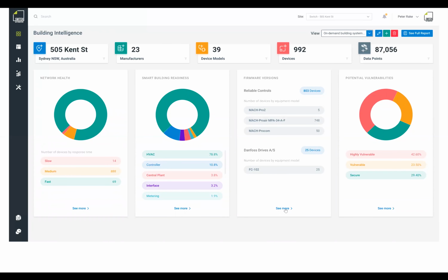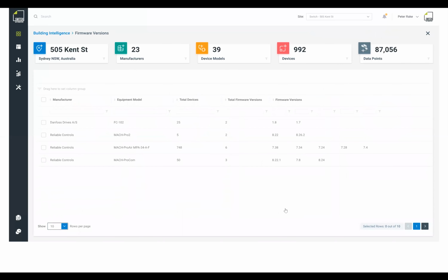Firmware is also another common potential vulnerability, with versions being really old, out of date, or exposing potential vulnerabilities. So in this scan here, you can see this particular piece of hardware had 5 different versions of firmware throughout this building. So now we're able to monitor this. You could get your vendor back out to upgrade the firmware to the current version, rerun this scanning tool, and be able to understand that, okay, all of my firmware versions have been consolidated into the latest.